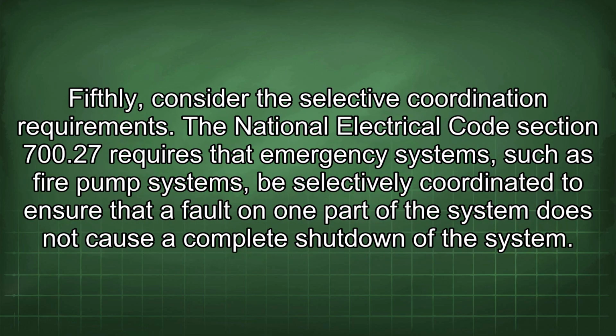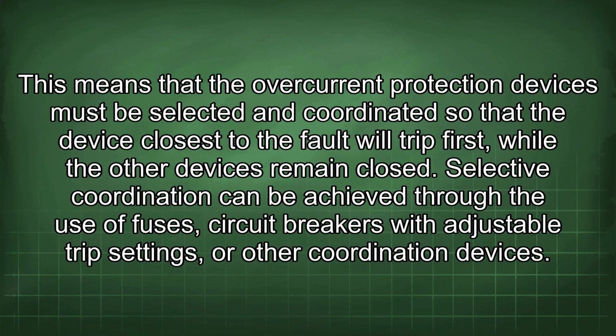Fifthly, consider the selective coordination requirements. The National Electrical Code Section 700.27 requires that emergency systems such as fire pump systems be selectively coordinated to ensure that a fault on one part of the system does not cause a complete shutdown of the system. This means that the overcurrent protection devices must be selected and coordinated so that the device closest to the fault will trip first, while the other devices remain closed. Selective coordination can be achieved through the use of fuses, circuit breakers with adjustable trip settings, or other coordination devices.